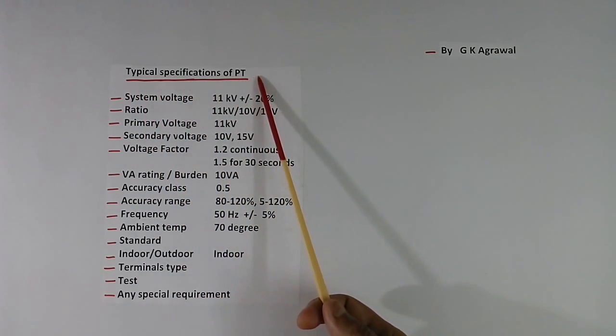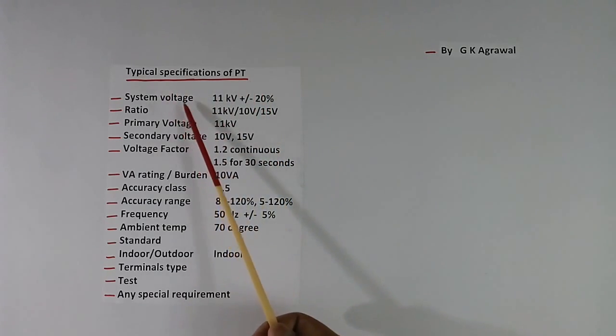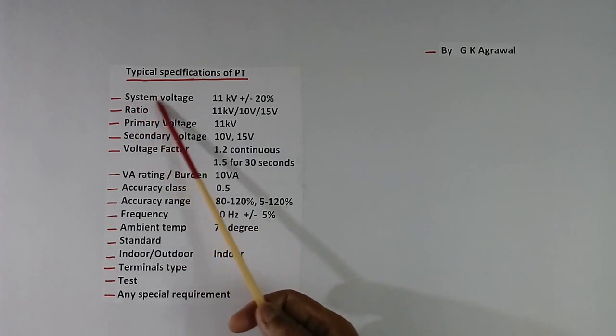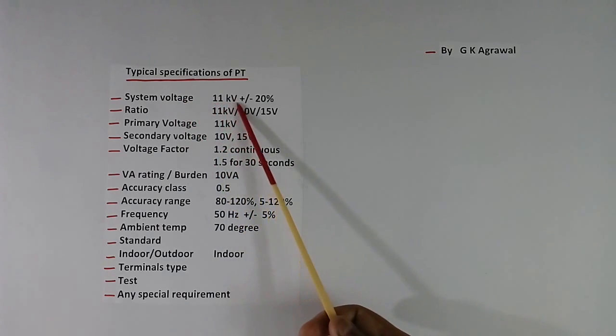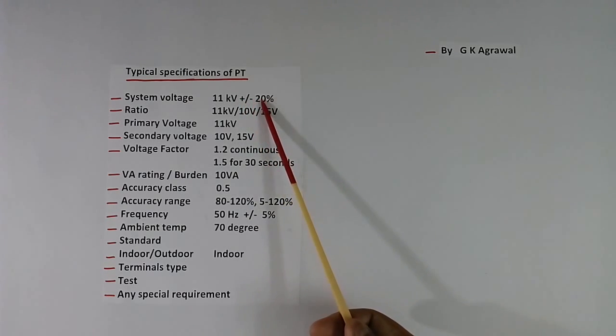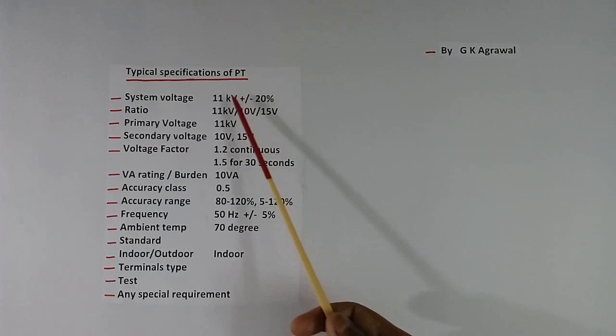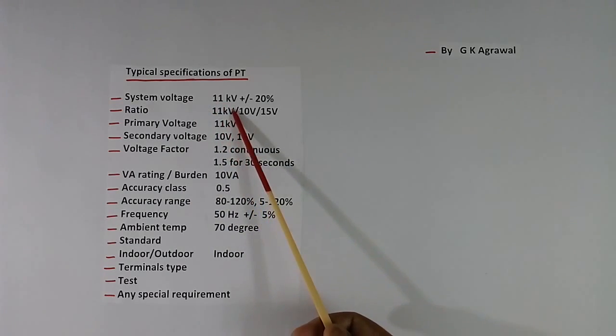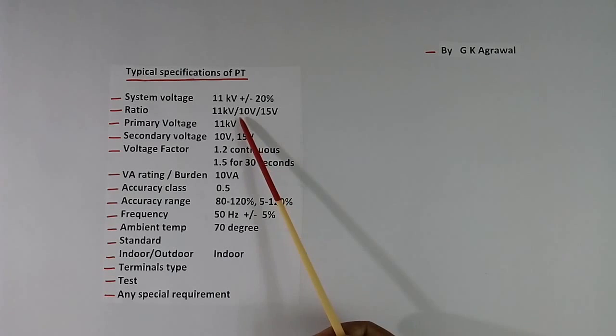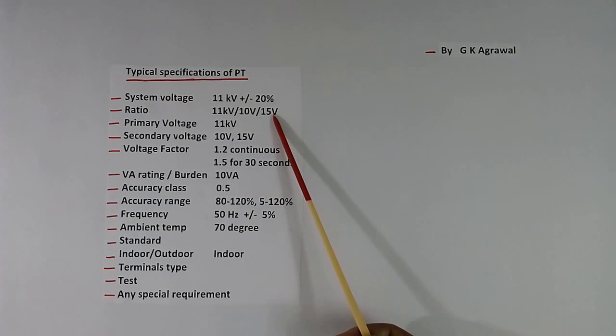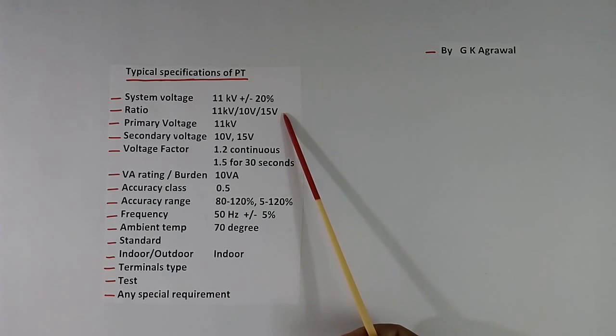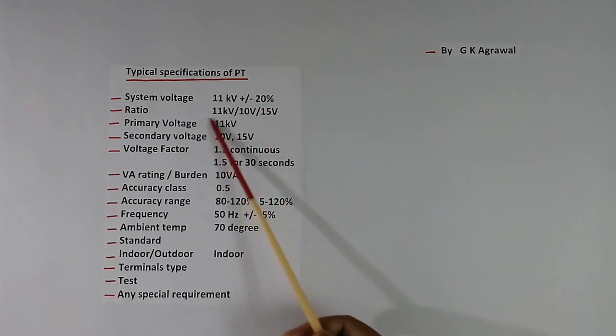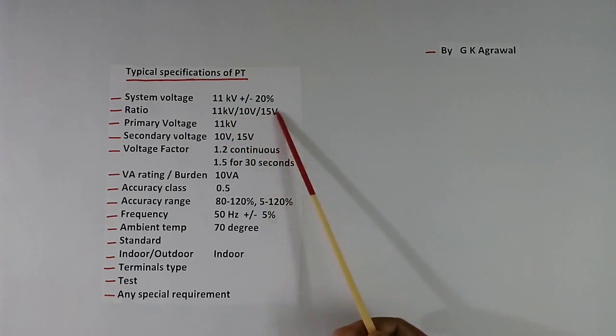Now we come to typical specifications. First, we have to give the system voltage — what is the voltage and what are the variations. The more the variation, the more expensive the transformer will be. Then the ratio — for example, primary voltage 11 kV. The secondary may have 2 windings: one may be 10 volts, another may be 15 volts. If you want a 3rd winding, you can specify that too. PT can have many secondary windings.